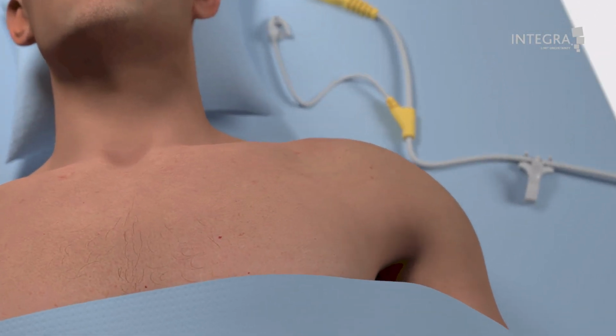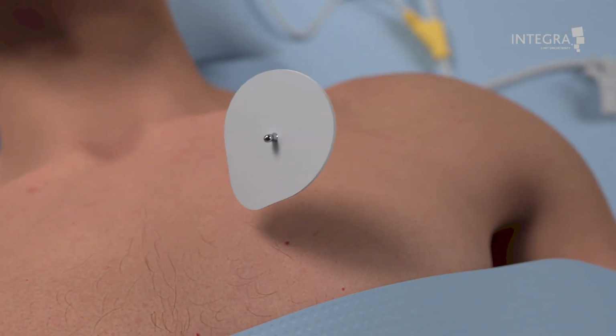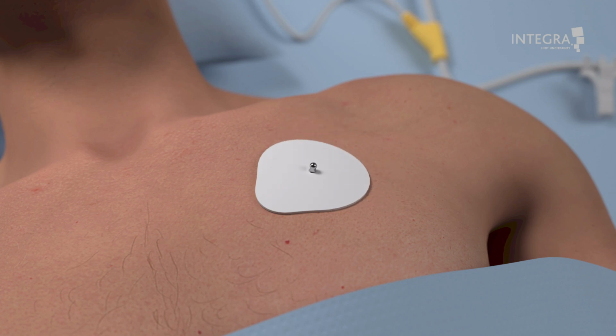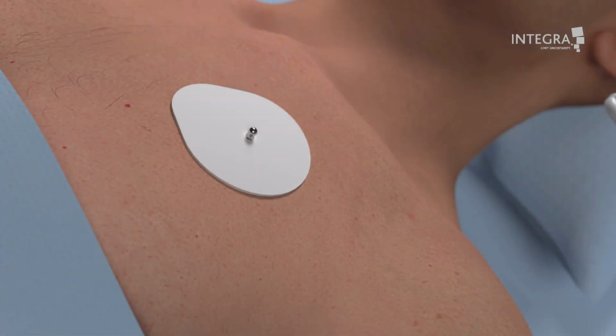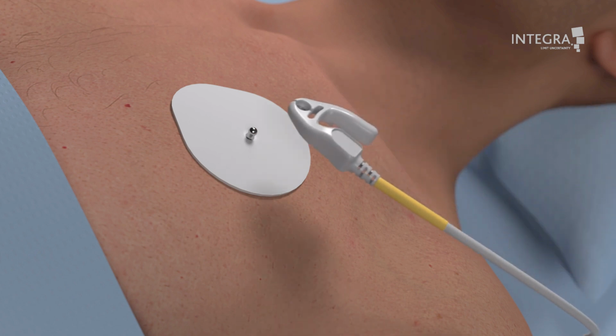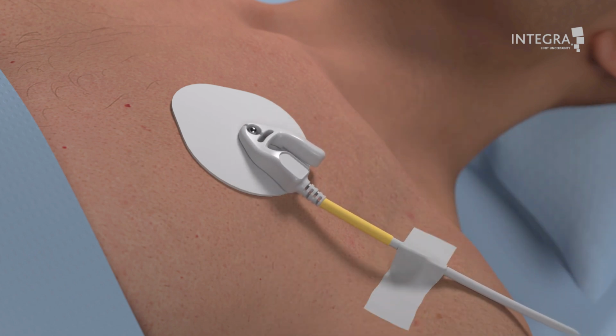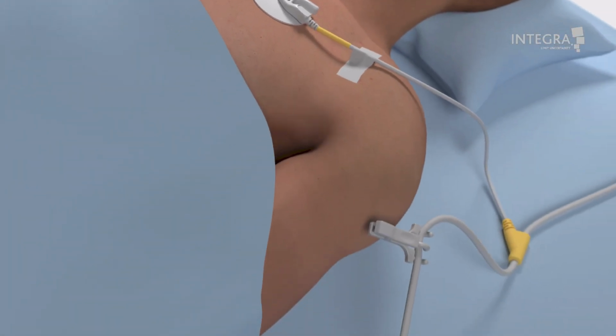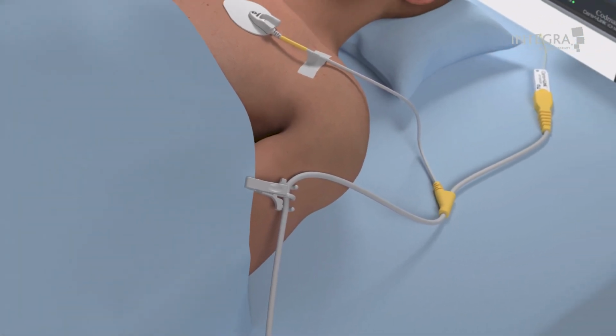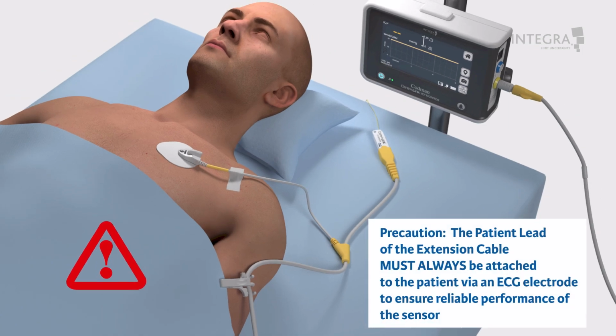Attach any off-the-shelf ECG electrode to the patient per the ECG electrode's instructions for use. ECG electrodes should be applied only to intact, clean skin. For example, not over open wounds, lesions, infected or inflamed areas. Attach the patient lead of the extension cable connector to the ECG electrode. Secure the patient lead of the extension cable to prevent tension on the ECG electrode. Precaution: the patient lead of the extension cable must always be attached to the patient via an ECG electrode to ensure reliable performance of the sensor.